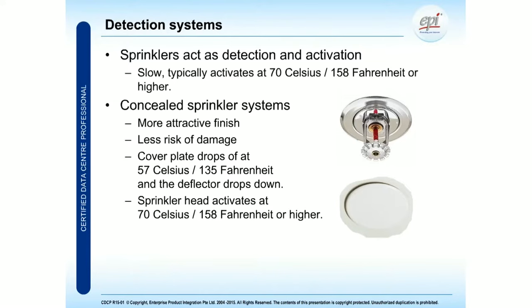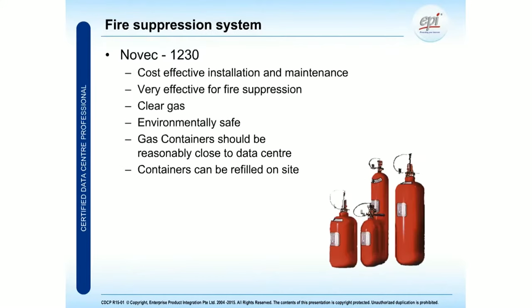This could be required by law, mandatory in some cases, but we prefer to use different systems inside our IT environment. One of these is called a VESDA system or an HSSD system, which we explain in the CDCP. It's a very good system - very sensitive, but also very reliable - and these systems can actually trigger your gas fire extinguishing system as well.